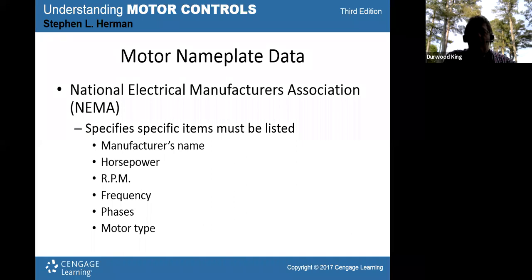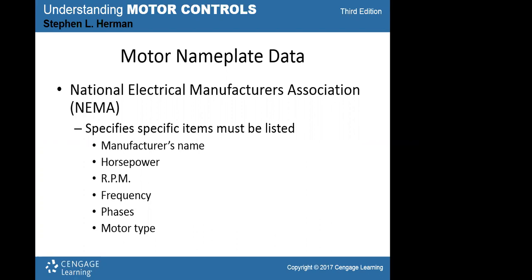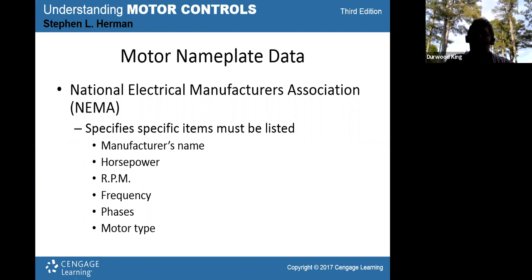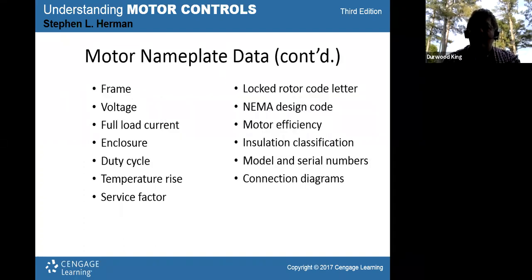Your manufacturer's name, your horsepower rating, your RPM, that's your revolutions per minute, the frequency that it accepts from the power line or from a VFD, and how many phases does it have? Is it single phase? Is it 2-phase, or is it 3-phase? And then the motor type, the construction of the motor internally. Is it a squirrel cage type motor internally on the windings, or is it a synchronous motor? Is it a wound rotor motor? When you're getting at the physical details of how the windings are made, then you're talking the type of motor. And motors are a world of their own, as you'll begin to see.